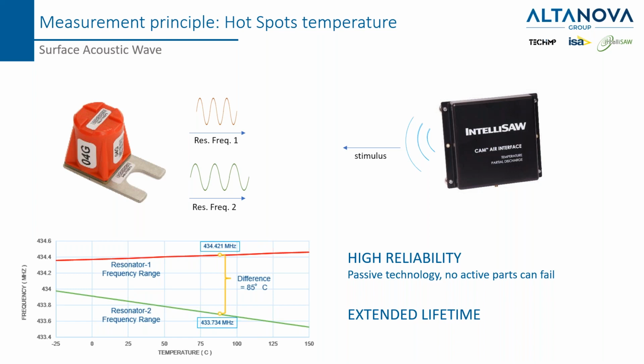This stimulus actually reaches the sensor that you can see on the left side, and the sensor, through the crystal and the technology it has inside, replies with two different resonance frequencies. Basically, these two frequencies are precise numbers, and the difference between these two frequencies represents the temperature measurement. This is because the crystal inside has a technology characteristic and behavior that, according to the temperature, gives a different resonator frequency.